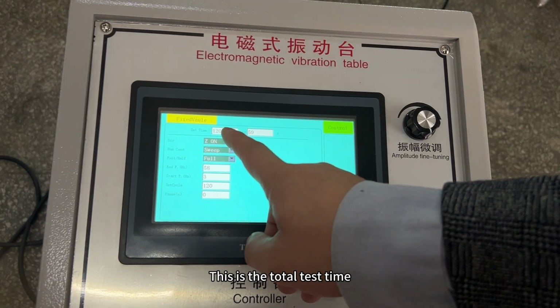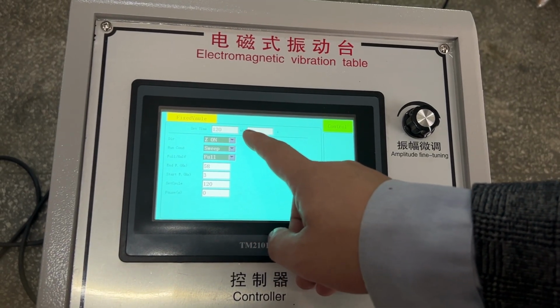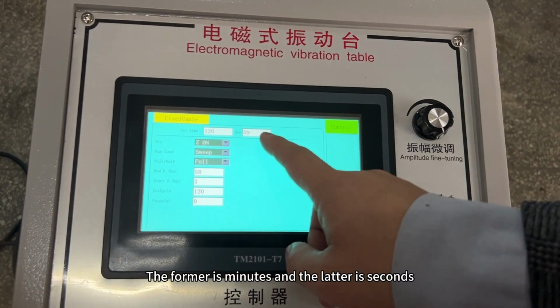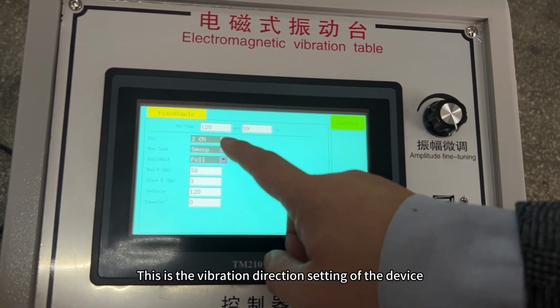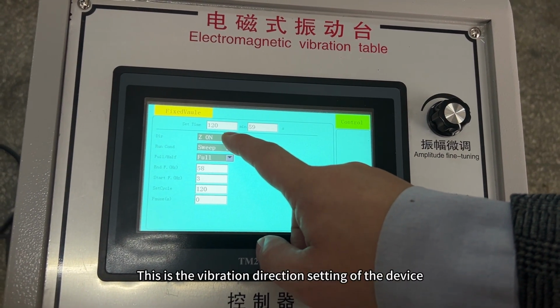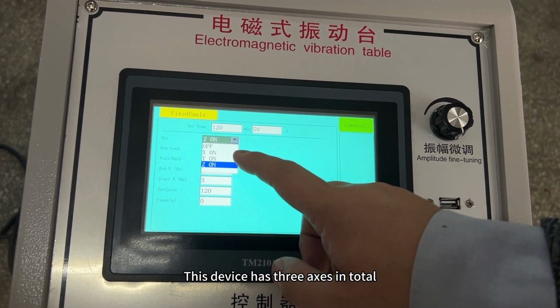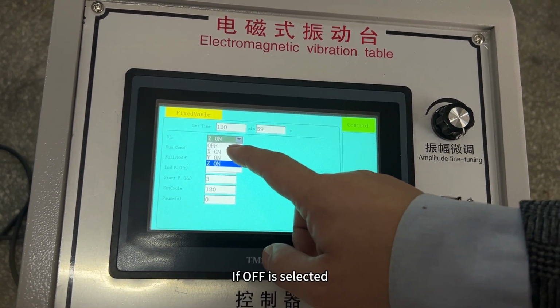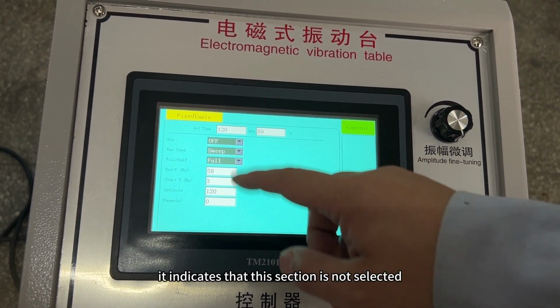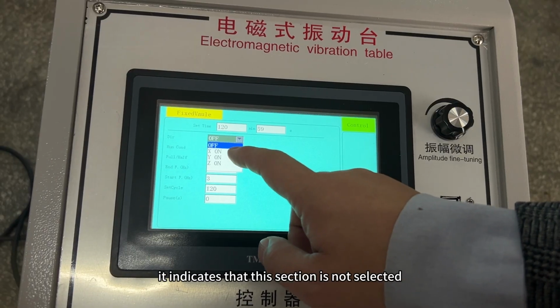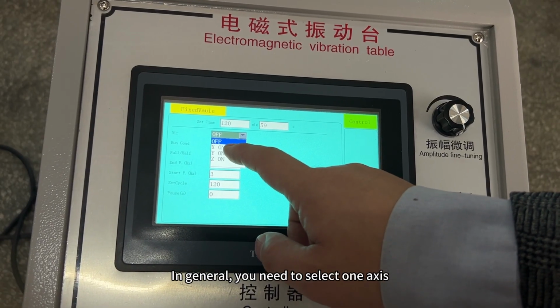This is the total test time. The former is minutes and the latter is seconds. This is the vibration direction setting of the device. This device has 3 axes in total. If off is selected, it indicates that this section is not selected. In general, you need to select one axis.